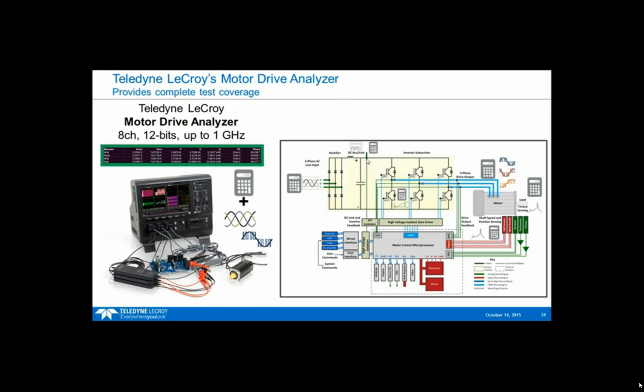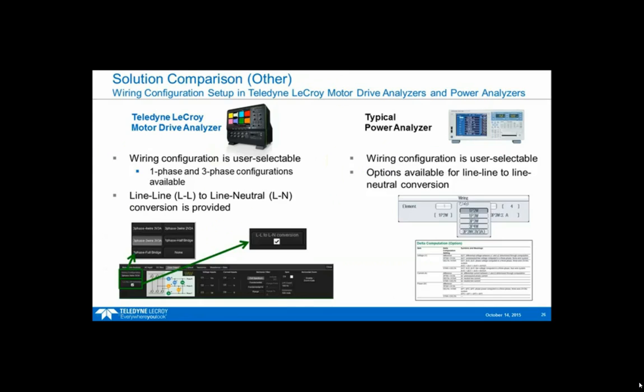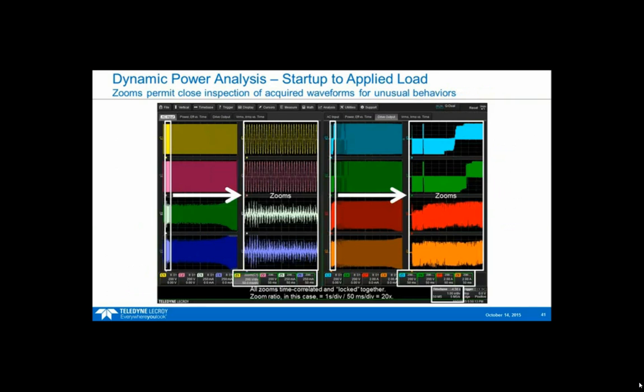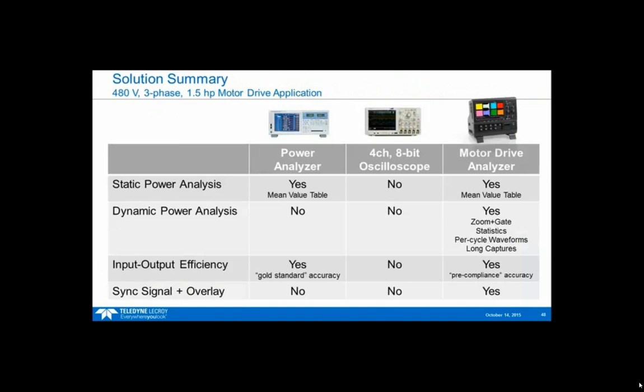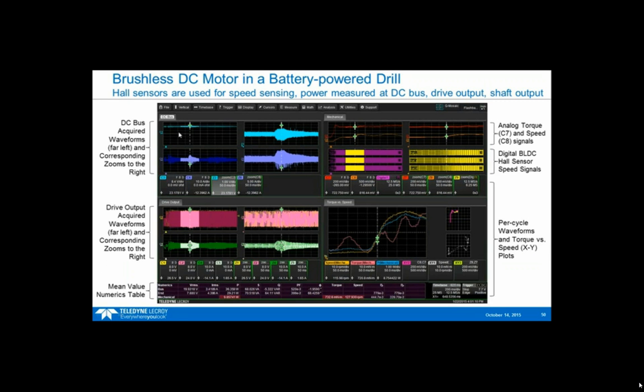As long as I can pick off a voltage and get a current probe or signal off this DC bus into my motor drive analyzer, I can get a table of those values as well. One example is that power tool example I had with the brushless DC motor. Here I used a voltage probe - this was only an 18 volt power tool, so I simply used a passive probe. I got the voltage right here, and this was a current signal - I used a conventional current probe, a 30 amp current probe. You could use other things as well, but you've got to be able to reach down to DC, of course.